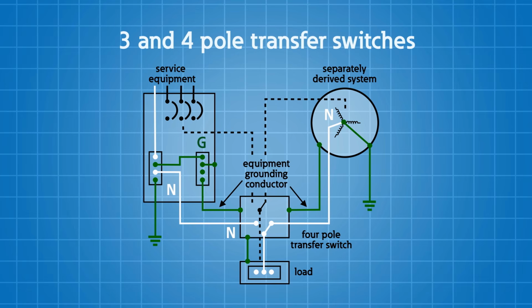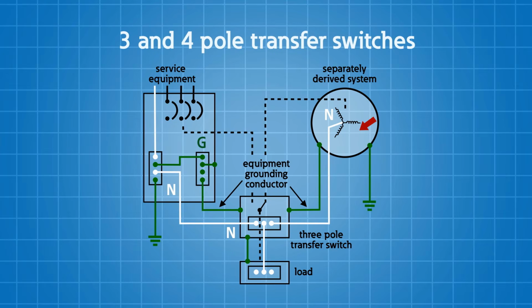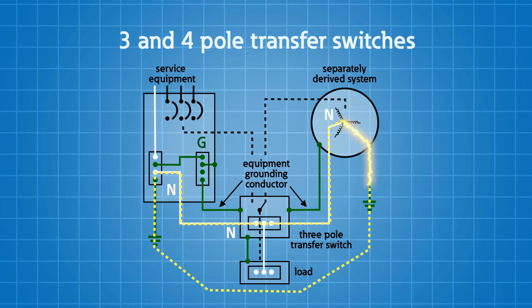But what if I accidentally bonded the neutral to the ground in the generator and I only have a 3-pole transfer switch? How do I fix it? Do I have to buy a 4-pole transfer switch? Sure, you could. Or you could simply unbond the neutral in the generator. But you must be extremely careful on how you operate a system like this, because the return current for the generator neutral will flow back through the other separately derived system or transformer. This is especially important for the electrical workers who will be servicing the equipment.